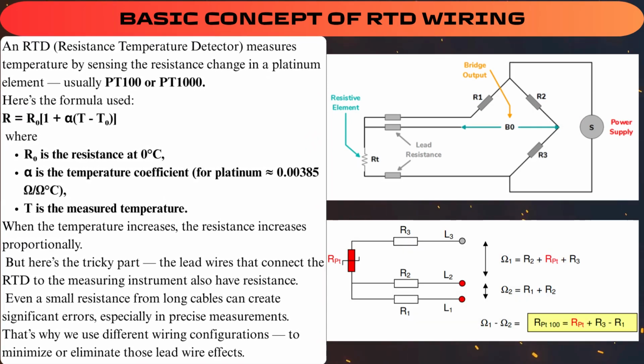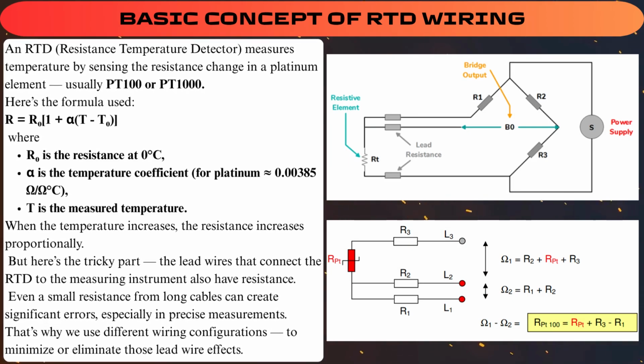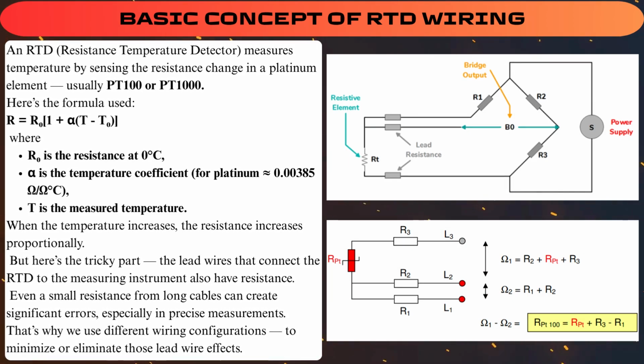An RTD, resistance temperature detector, measures temperature by sensing the resistance change in a platinum element, usually PT100 or PT1000. Here's the formula used: R = R0(1 + alpha T), where R0 is the resistance at 0 degrees Celsius, alpha is the temperature coefficient for platinum, 0.00385 ohm per degree C, and T is the measured temperature. When the temperature increases, the resistance increases proportionally.